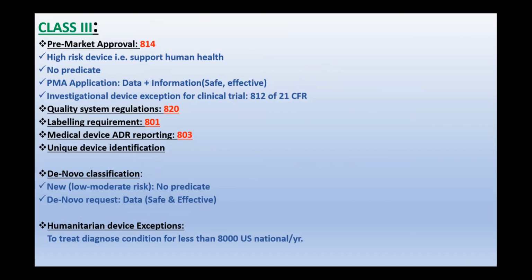Along with that, an investigational device exemption is needed for the clinical trial under Part 812 of 21 CFR. The device has to meet the quality system regulations as per 820. The labeling requirements have to be met as per Part 801 of 21 CFR. The medical device adverse event reporting has to be met as per 803.